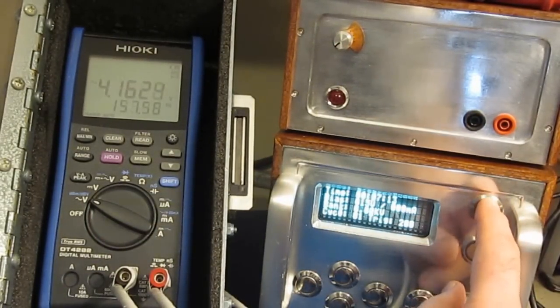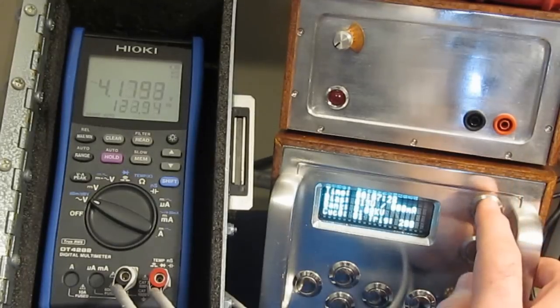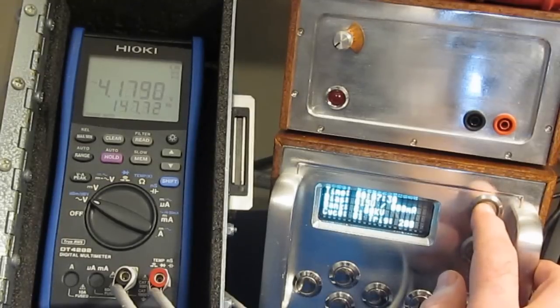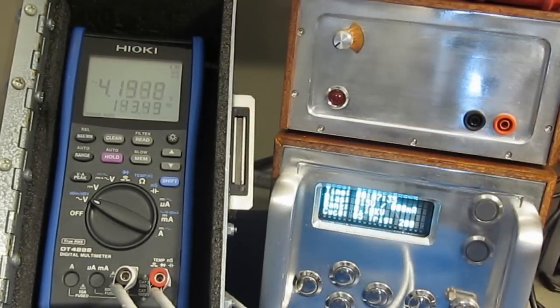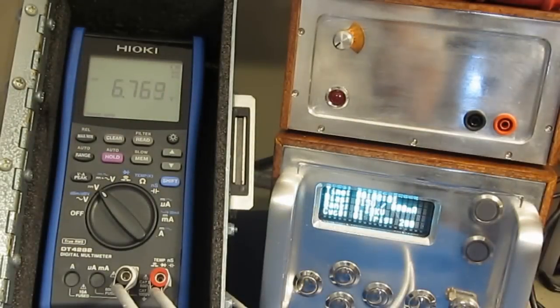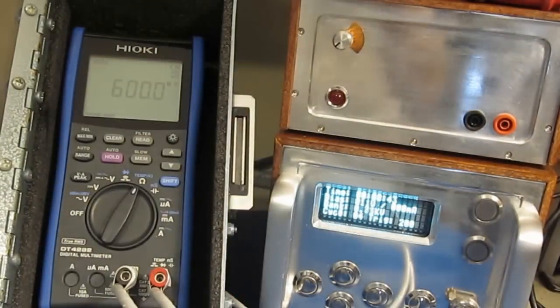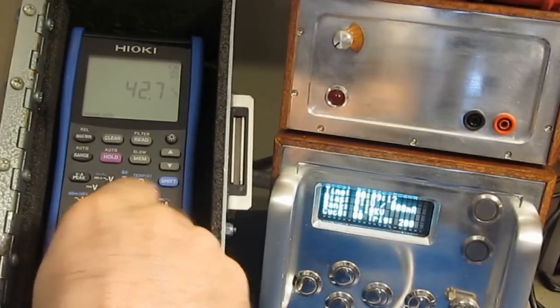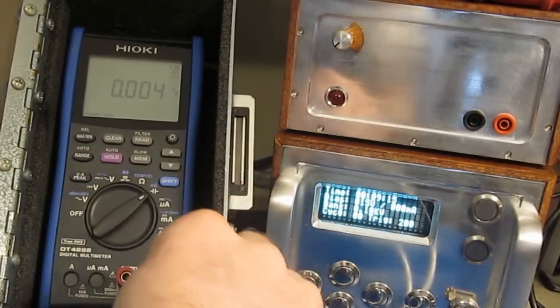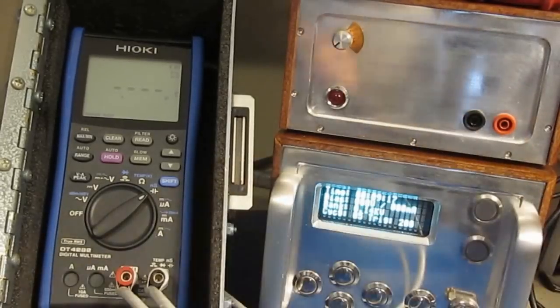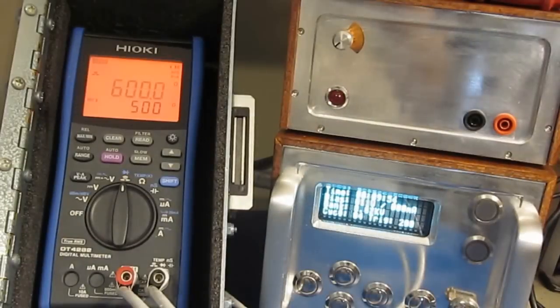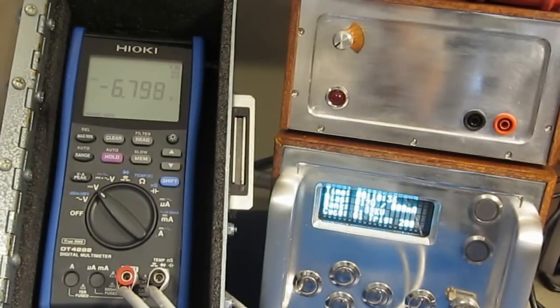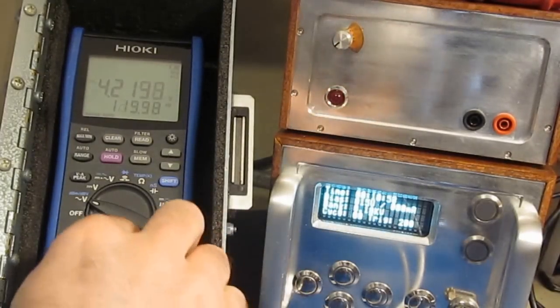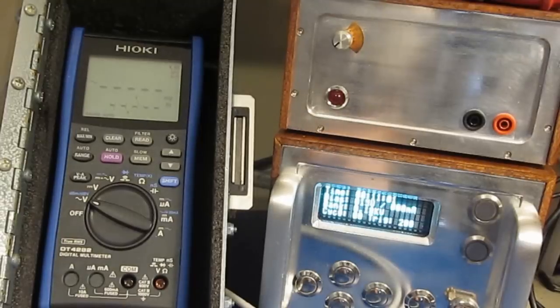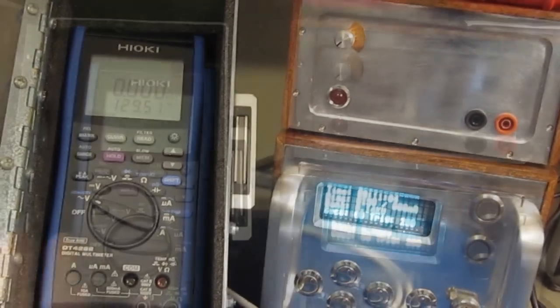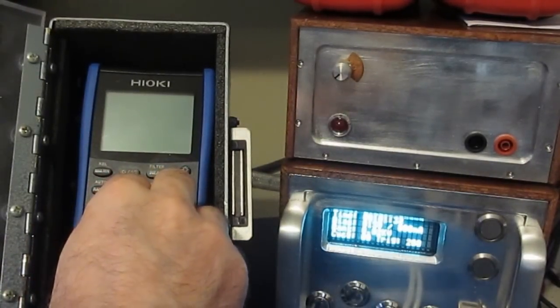Anyway, so here we go. This will be our first 5 transients. Again, this will be a 1000 volt peak with 100 microsecond full width half height and a 2 ohm source impedance. Then we have to invert the leads to get the negative transient. Okay, that's it. I'll go ahead and functional test the meter. So our Hioki survived the 1000 volt peak.